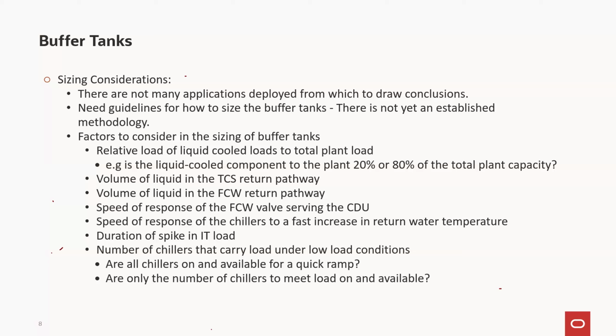If you have enough pipes, you may not need a tank. Right. Except for the fact that the tank has this valuable pro of working as a low-pass filter, smoothing the shape of the heat front, which becomes a slower increase instead of a sudden step, as you described before. But in the end, I think that the math behind the tank is to compare the time that it takes to go from the cluster to the heat exchanger with the time it takes to turn on the cooling system and bring its water to the heat exchanger.